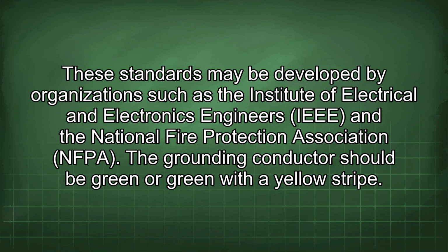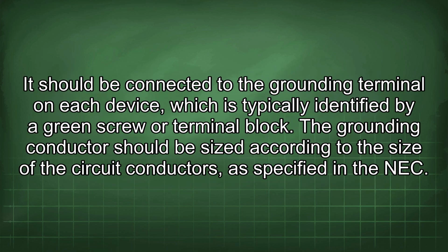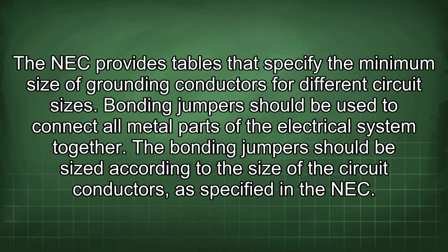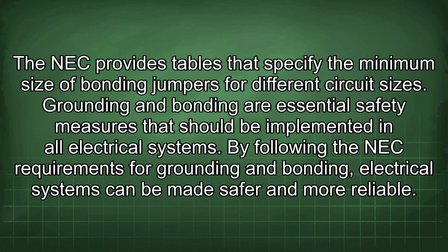The grounding conductor should be green or green with a yellow stripe. It should be connected to the grounding terminal on each device, which is typically identified by a green screw or terminal block. The grounding conductor should be sized according to the size of the circuit conductors, as specified in the NEC. The NEC provides tables that specify the minimum size of grounding conductors for different circuit sizes. Bonding jumpers should be used to connect all metal parts of the electrical system together. The bonding jumpers should be sized according to the size of the circuit conductors, as specified in the NEC. The NEC provides tables that specify the minimum size of bonding jumpers for different circuit sizes.